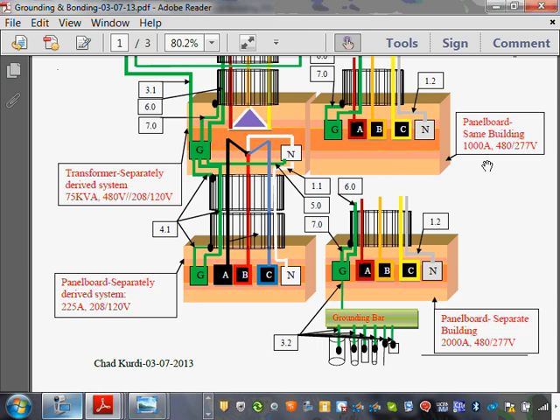So, from an OSHA point of view or 70E point of view, what's the difference between getting into here? Well, if you put it here or here, from 70E, now you are on the line side of the disconnect on both sides, which means you are exposed to almost the same amount of arc flash, arc blast. When you're in this panel, you are exposed to the arc that could come from the line side of the disconnect. You could arc the line side, not the load side. So from an arc point of view, you're exposed to the same hazard.